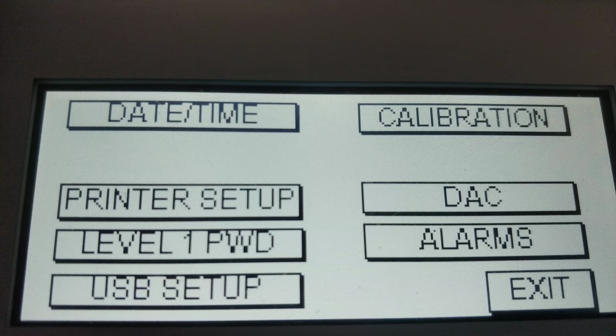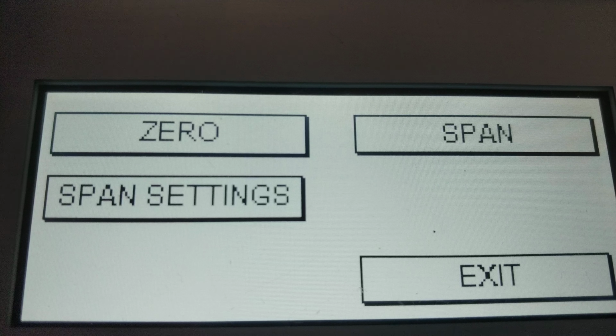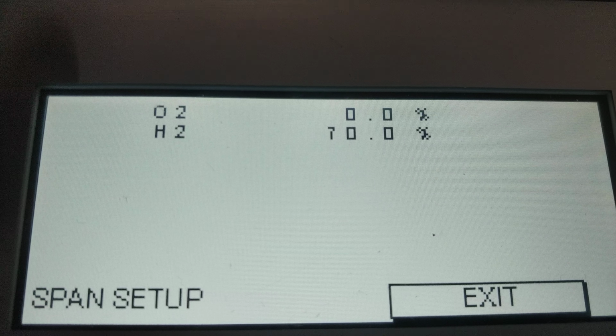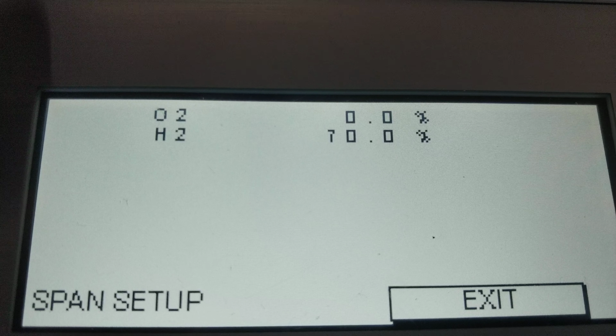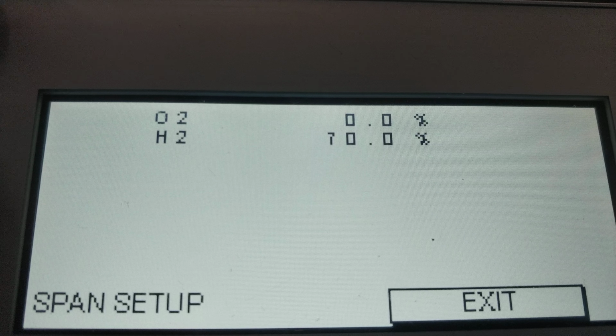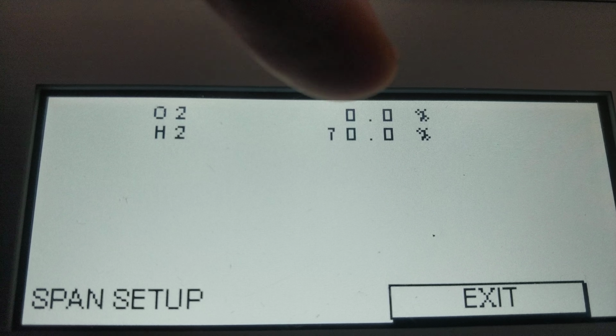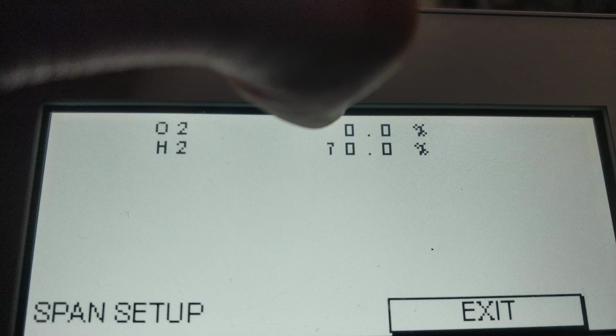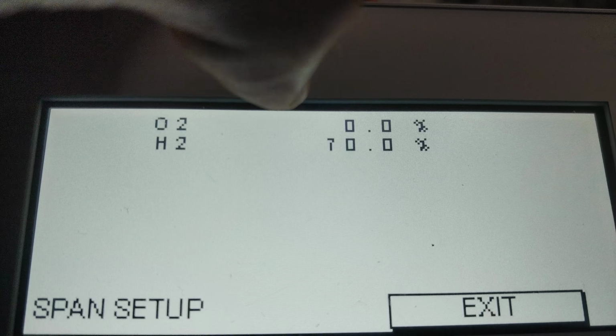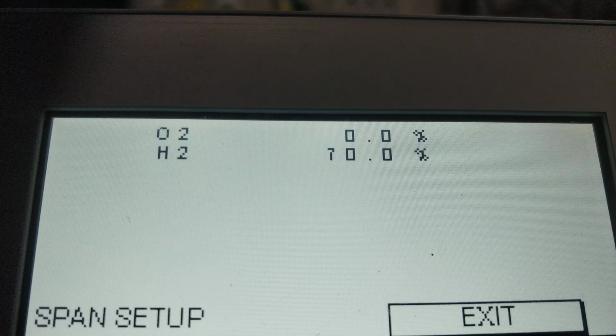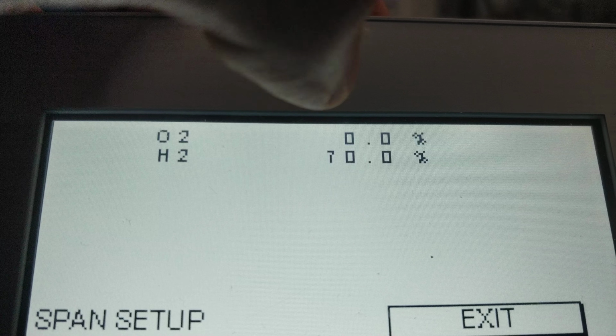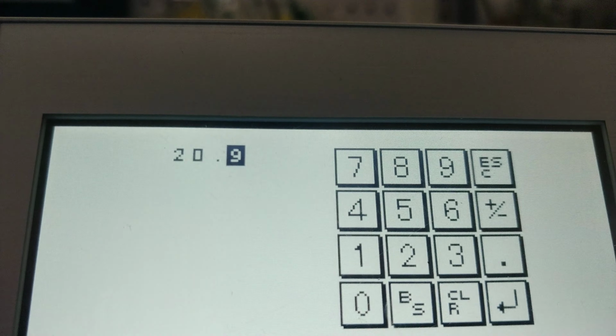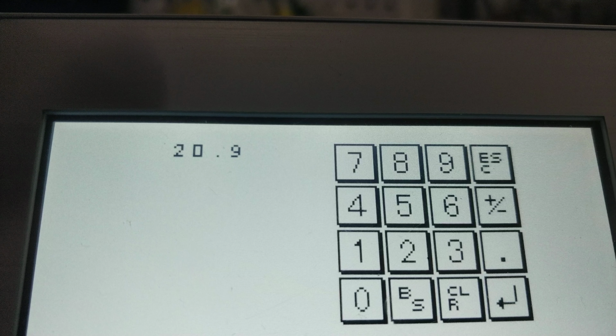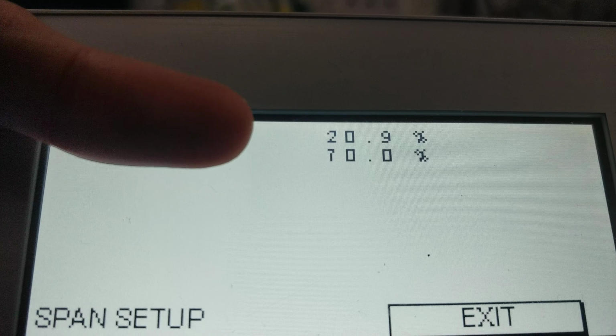Before we do that, we just want to check a couple of things here. In this menu here, span settings, you want to put down what the values are and what you're calibrating against. In this case, since we're going to be using ambient air, we want to set this to 20.9, and then the H2 you set to whatever you have in your cylinder for H2. In our case we've put 70; in your case you will put down whatever's in your cylinder. So first thing, I'm going to change the O2 to 20.9. 20.9 is, relatively speaking, the oxygen concentration in ambient air, so we're going to use this. Now we have 20.9 and 70.0.